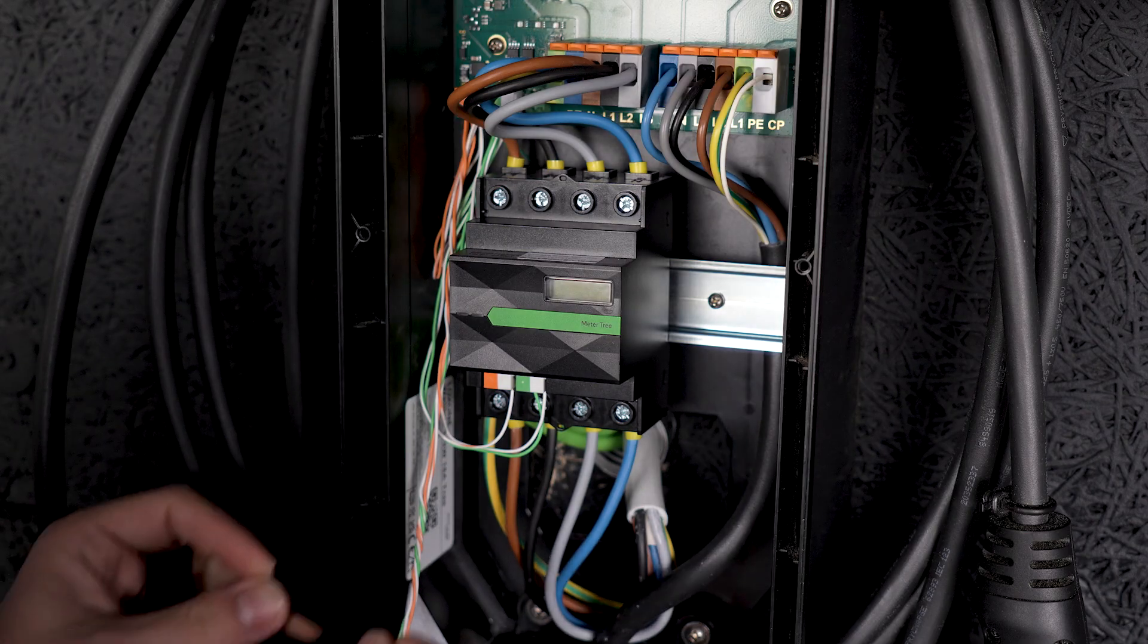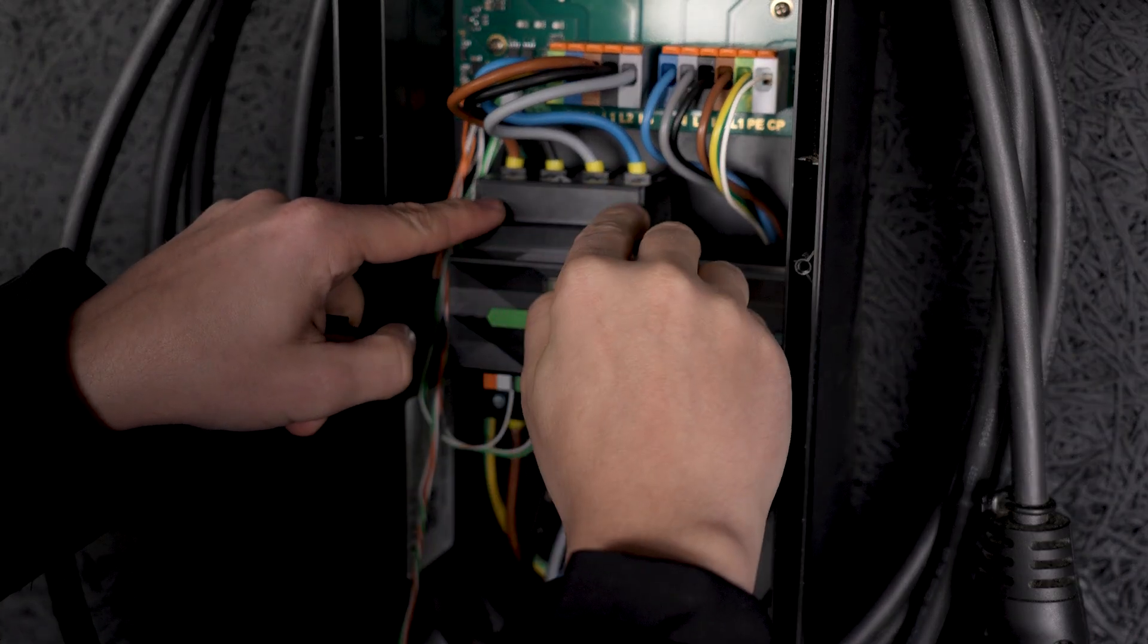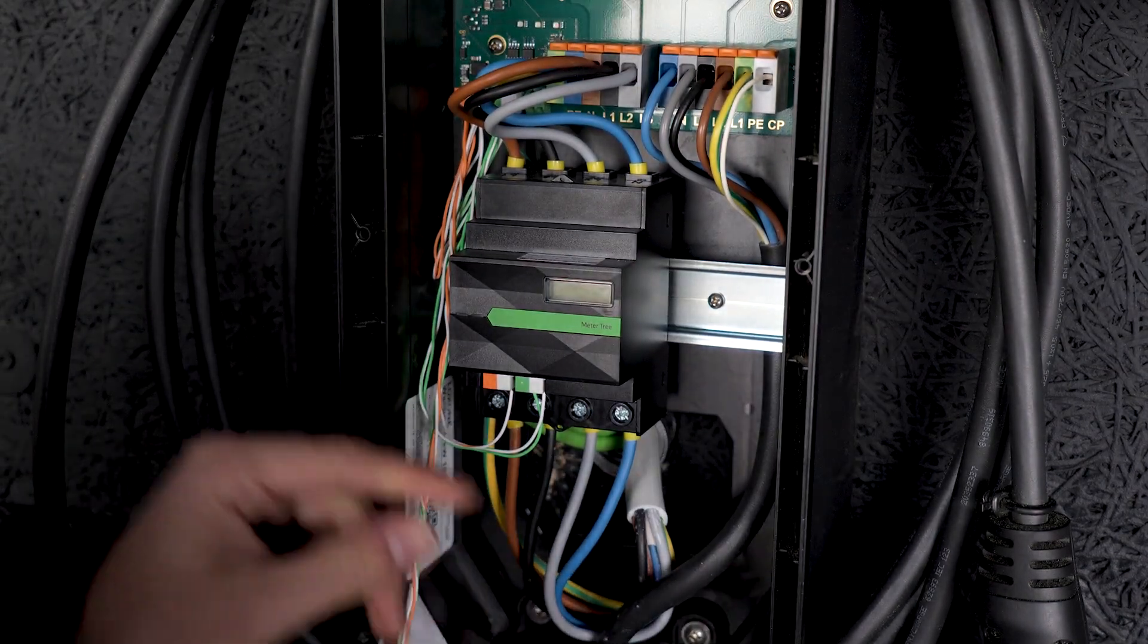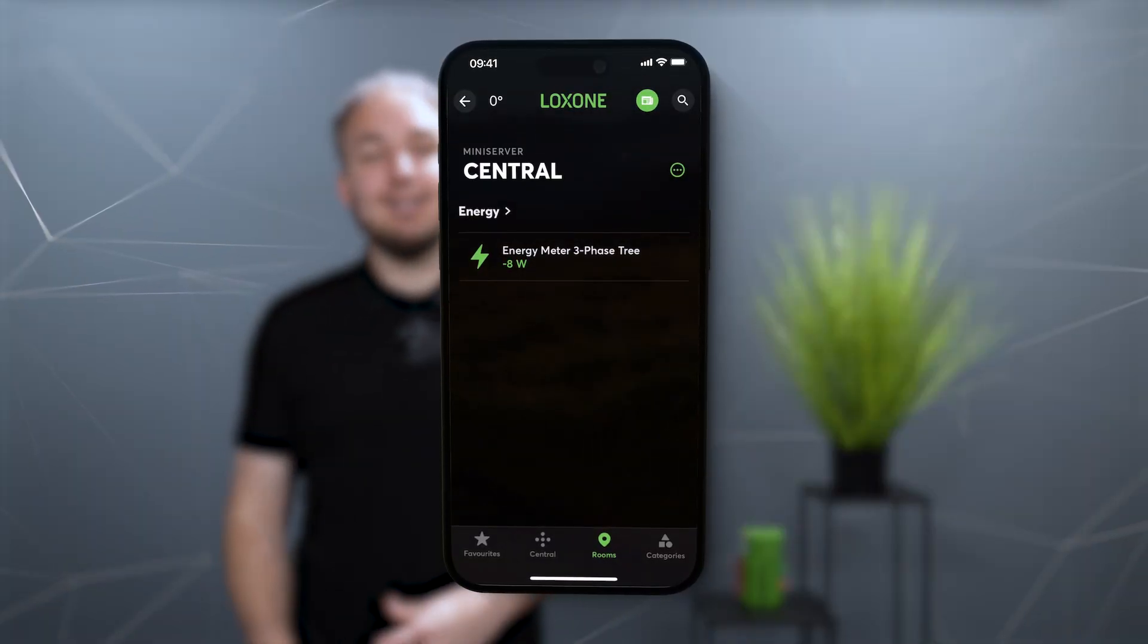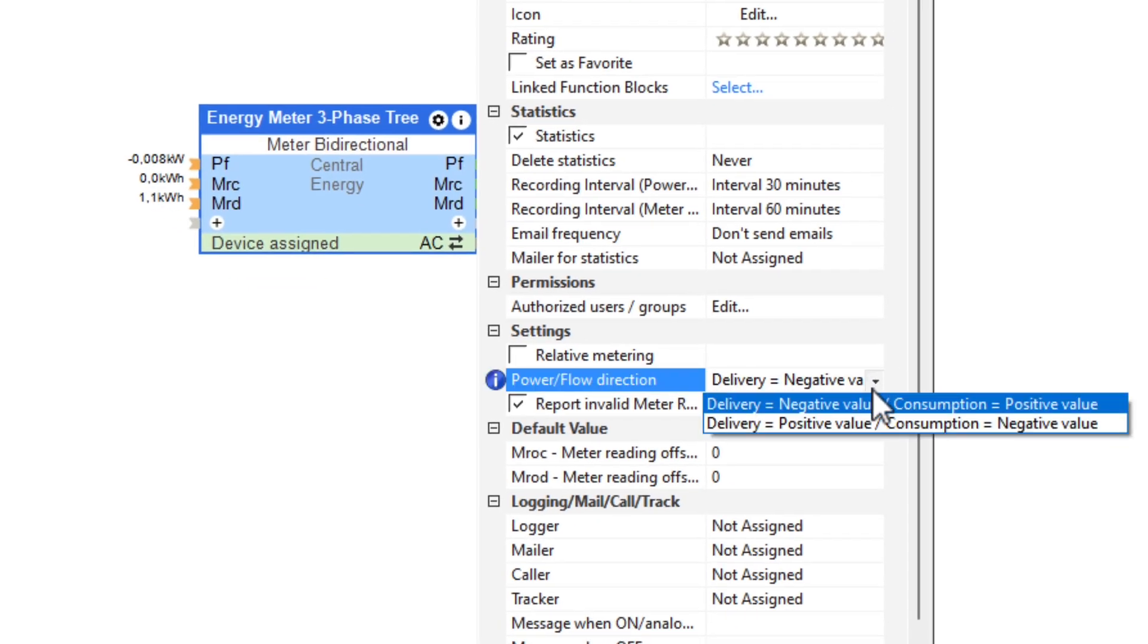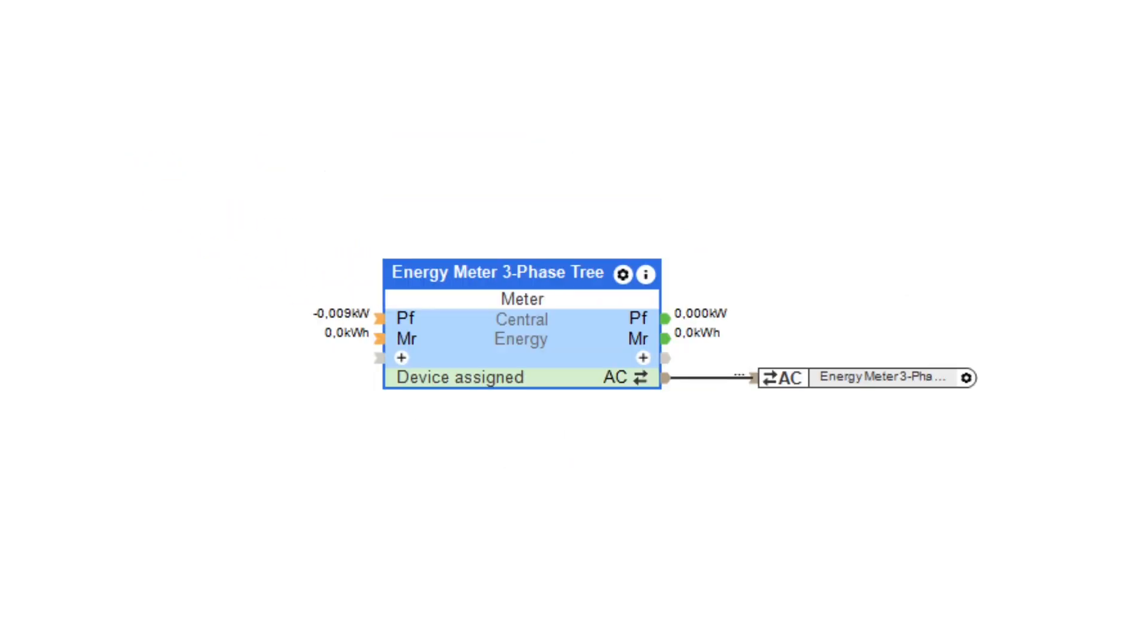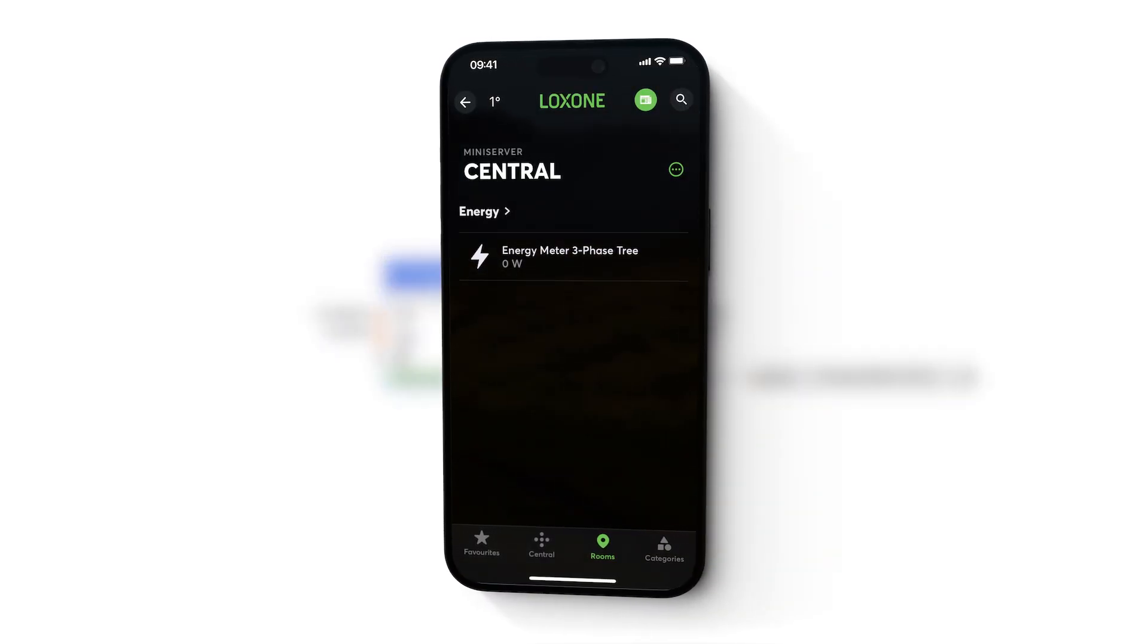When connecting the meters, it makes no difference whether the supply line is connected from below or from above as recommended on the housing. If the values in the visualization are displayed with a wrong sign, this can be changed in the software with just one click. When using a unidirectional meter, a negative value would also be displayed as zero.